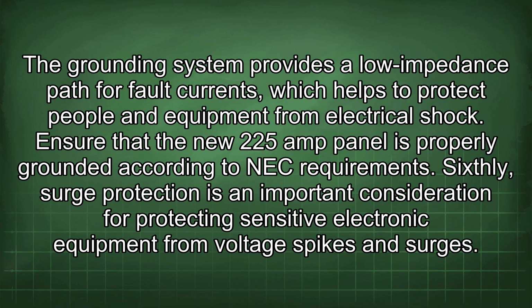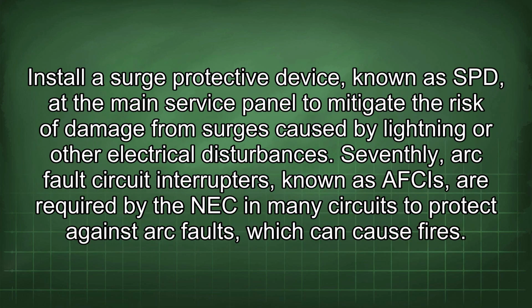Sixthly, surge protection is an important consideration for protecting sensitive electronic equipment from voltage spikes and surges. Install a surge protective device, known as SPD, at the main service panel to mitigate the risk of damage from surges caused by lightning or other electrical disturbances.